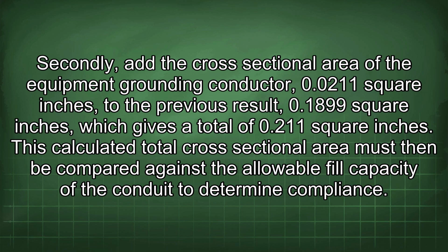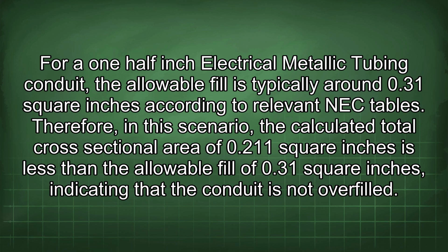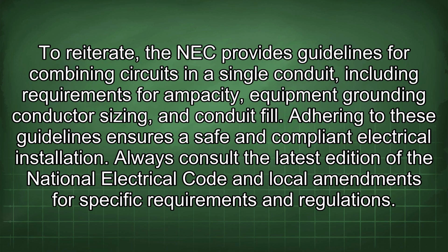This calculated total cross-sectional area must then be compared against the allowable fill capacity of the conduit to determine compliance. For a 1/2 inch electrical metallic tubing conduit, the allowable fill is typically around 0.31 square inches according to relevant NEC tables. Therefore, in the scenario, the calculated total cross-sectional area of 0.211 square inches is less than the allowable fill of 0.31 square inches, indicating that the conduit is not overfilled. To reiterate, the NEC provides guidelines for combining circuits in a single conduit, including requirements for ampacity, equipment grounding conductor sizing, and conduit fill. Adhering to these guidelines ensures a safe and compliant electrical installation.